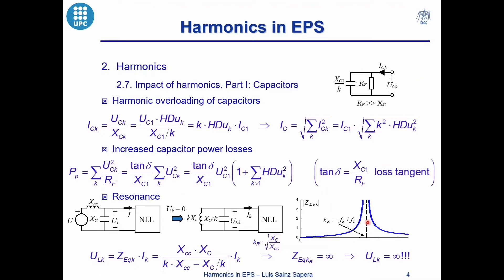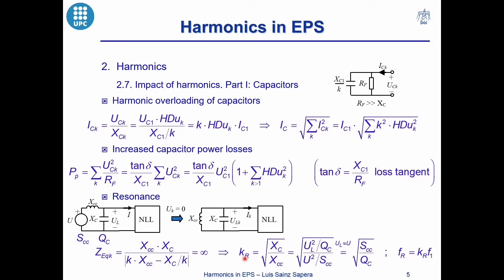At this harmonic the values of the harmonic voltages are also infinite. We have a parallel resonance phenomenon at this harmonic, which is related to a maximum of the equivalent impedance and may produce high values of the harmonic voltages. These high values may increase the harmonic overloading and power losses of the capacitors. The harmonic order of this resonance can also be calculated from the short-circuit power of the grid and the reactive power of the capacitor bank, and the resonance frequency can be determined from this harmonic and the fundamental frequency of the installation.